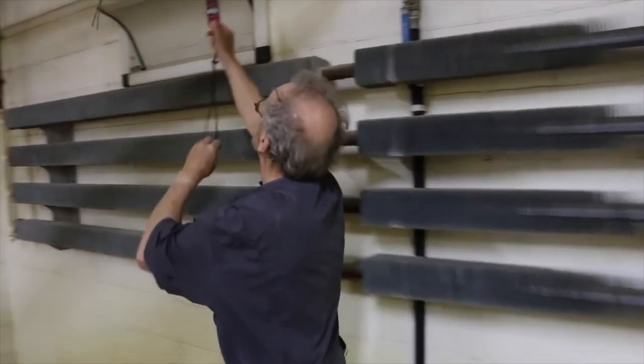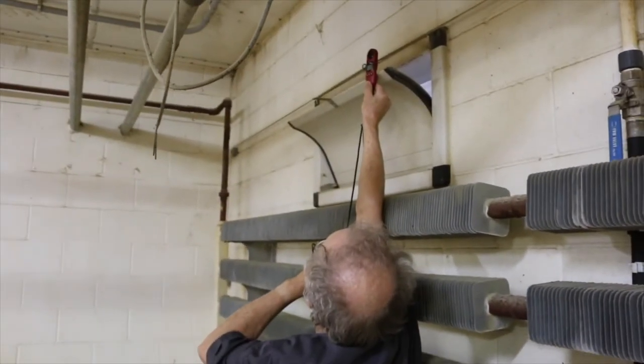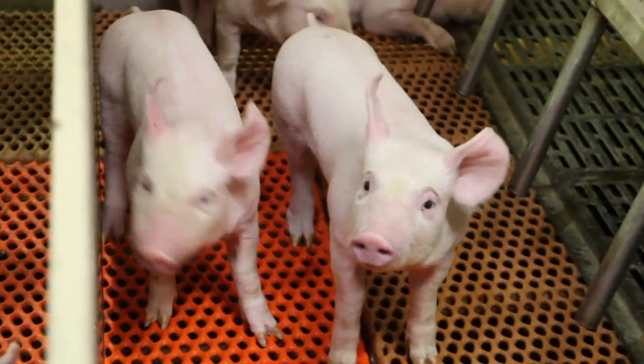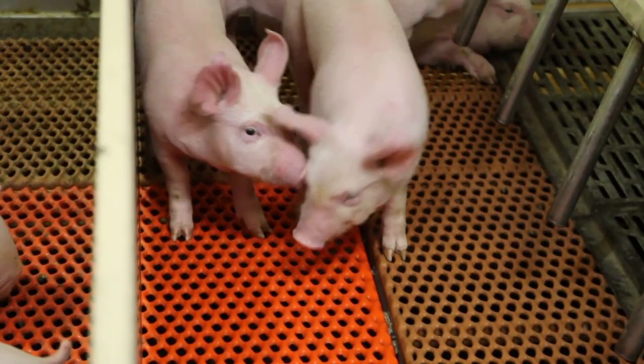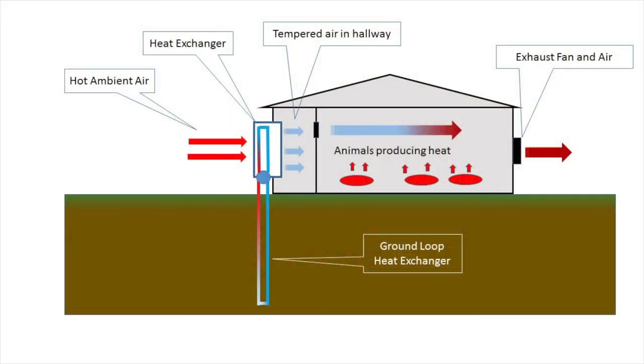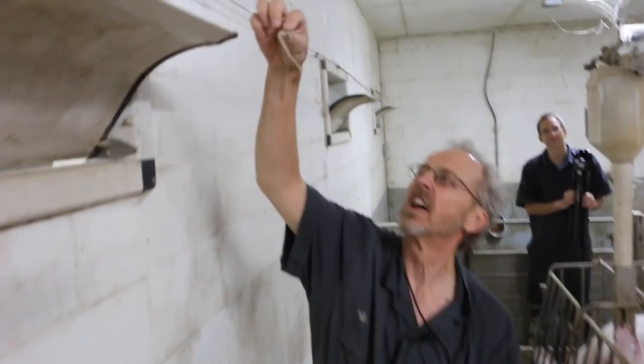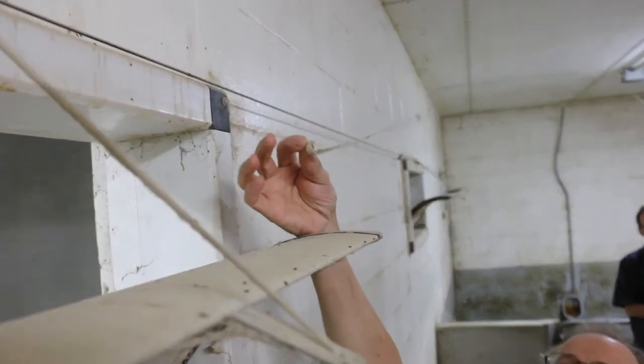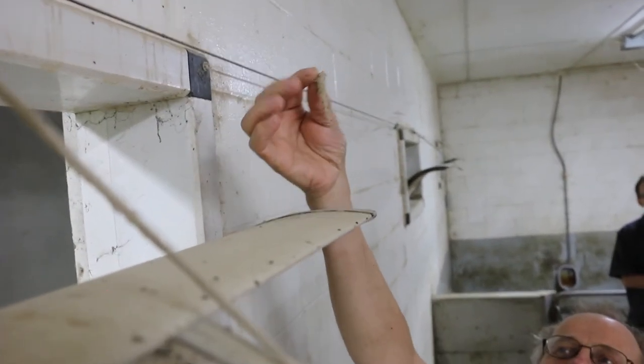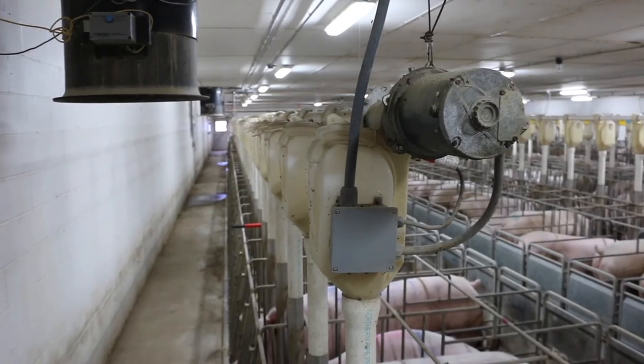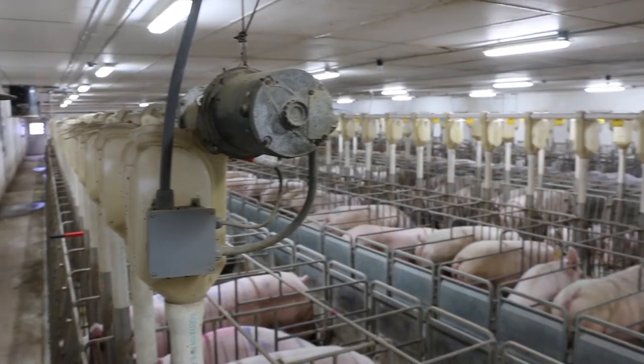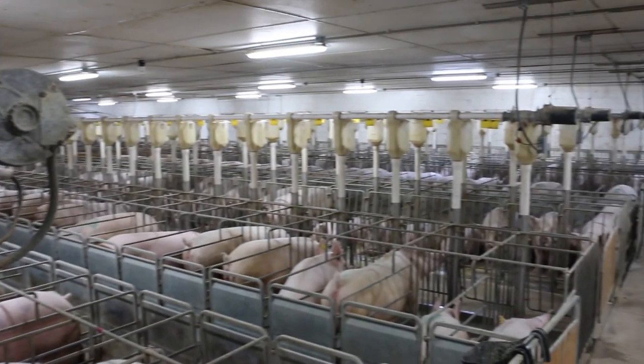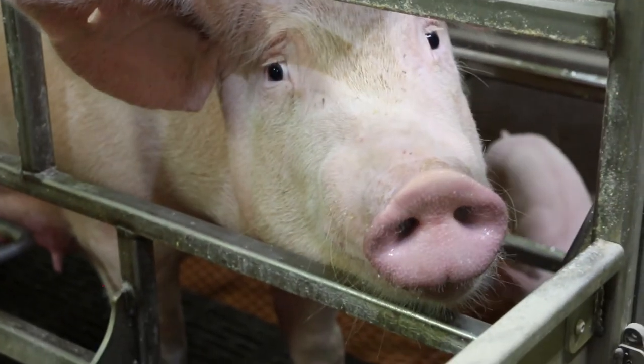These geothermal systems are not only used to cool the warm inlet air during the summer, they can also be used to warm the cold inlet air during the winter. This is because the water coming into the heat exchanger from the ground is at a constant temperature of about 50 degrees Fahrenheit year-round. We can show that there is actually airflow. The costs of installing a geothermal system may be offset by the lower cost of operating the ventilation system or by the reduced need for supplemental heat in cold weather. The costs may also be offset by improved animal performance if heat stress is reduced.